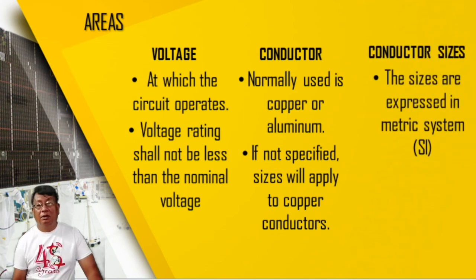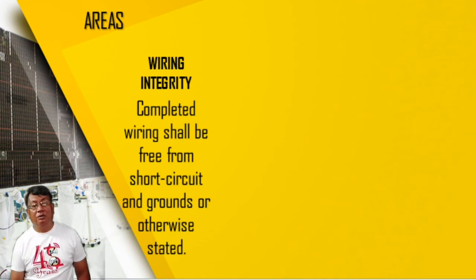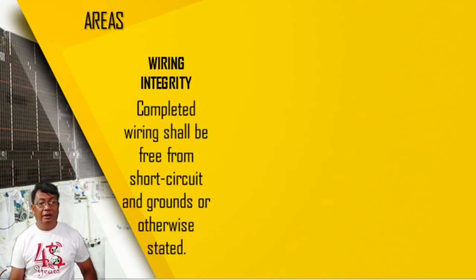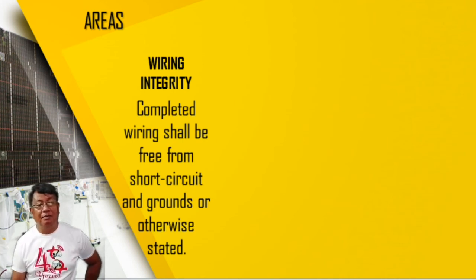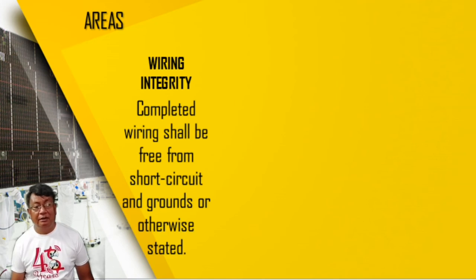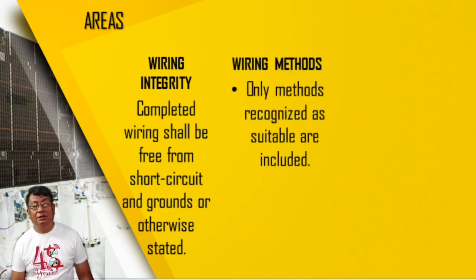Okay. So conductor sizes, the sizes are expressed in metric system, or we call this SI, the International Standard Metric System. Talking about wiring integrity. So we have this: completed wiring shall be free from short circuits and grounds, or otherwise stated. Okay. So completed wiring shall be free from short circuits. So testing should be done. Okay. We have wiring methods. Only methods recognized as suitable are included.